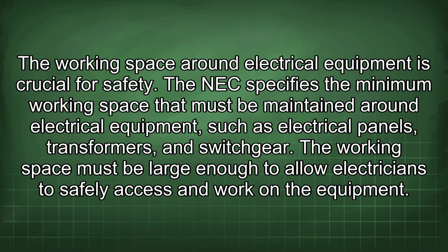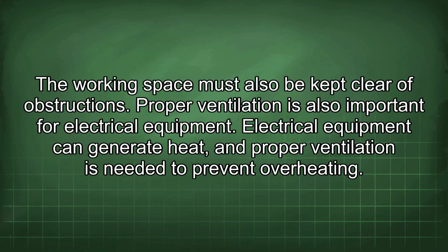The working space around electrical equipment is crucial for safety. The NEC specifies the minimum working space that must be maintained around electrical equipment, such as electrical panels, transformers, and switchgear. The working space must be large enough to allow electricians to safely access and work on the equipment. The working space must also be kept clear of obstructions.